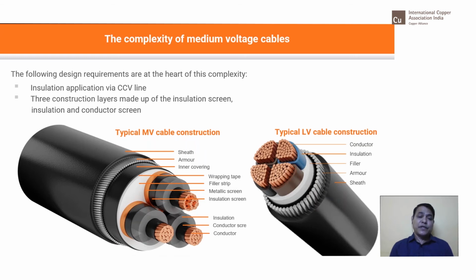So, the conductor screen, insulation screen, and the main insulation are done in one process in a CCV line, continuous catenary vulcanization, we call it CCV full form. Whereas the low voltage looks a very simple design, until the laying up stage or until the bedding. Before the bedding, the two are different, but after the bedding, normally they could be the same.